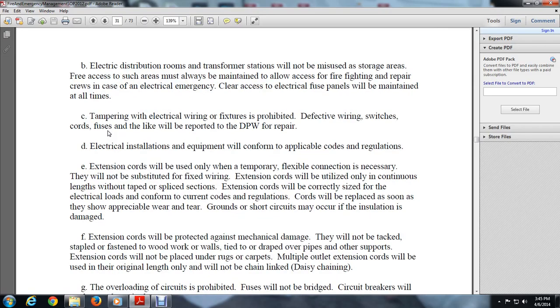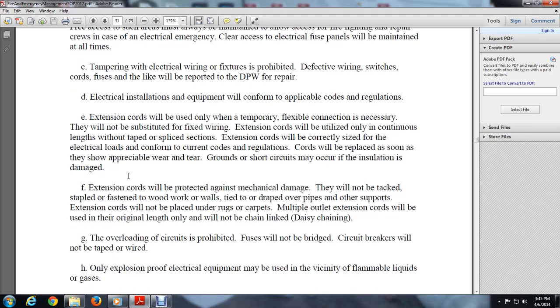Extension cords will be used only for temporary relief, where a flexible connection is necessary, and will not be substituted for fixed wiring. Extension cords will be utilized in continuous lengths without taped or spliced sections. Extension cords will be correctly sized for the electrical load and conform to current code regulations. Cords will be replaced as soon as they show wear and tear, since a grounding fault or short circuit may occur and damage the installation. Extension cords will be protected against mechanical damage. They will not be tacked or stapled, fastened to wood, or tied to drapes, pipes, or supports. Extension cords will not be placed under rugs or carpets.